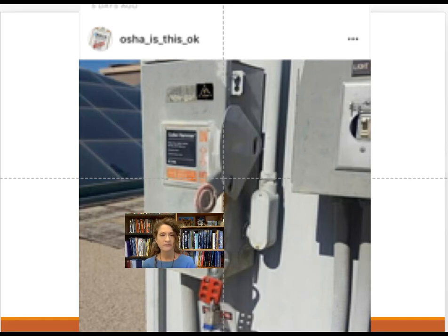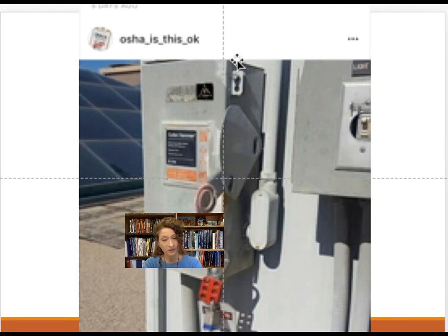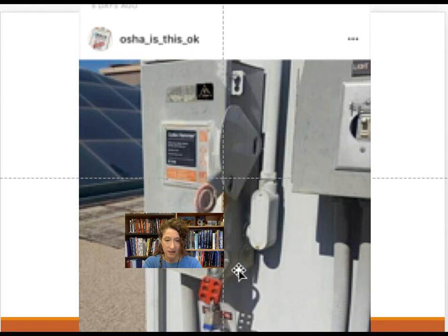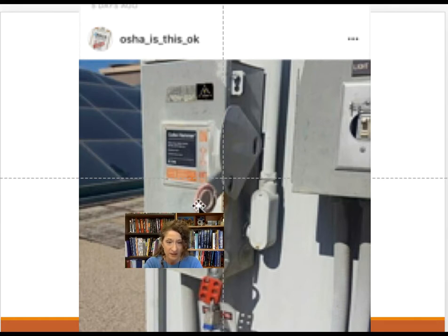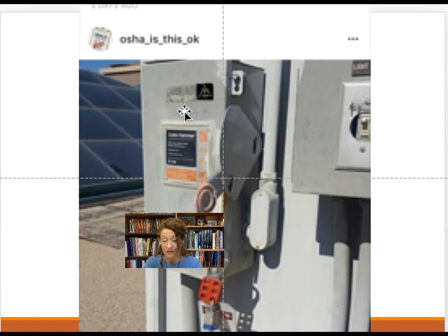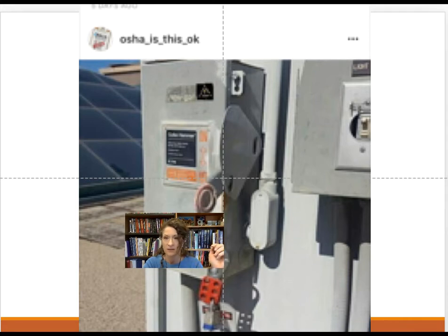Here is an example from an Instagram account called OSHAIsThisOK. You can see the way you would turn on the electrical device — on and off — and this is actually the way you open the box. The lockout-tagout device is on the way to open the box, which is done properly, but it does nothing to prevent accidentally turning on the equipment. This is an OSHA fail. You need to lock out and tag out this device so you can't accidentally turn it on. Also, this isn't labeled appropriately, which is also a lockout-tagout fail.